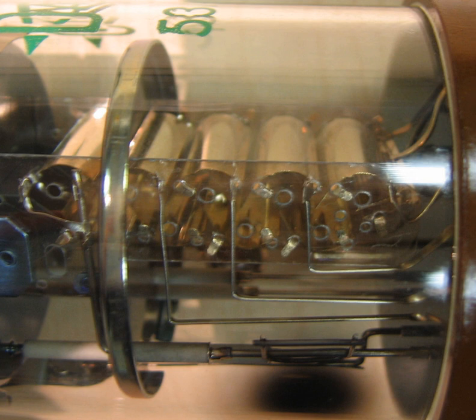The photocathodes can be made of a variety of materials, with different properties. Typically the materials have low work function and are therefore prone to thermionic emission, causing noise and dark current, especially the material sensitive in infrared. Cooling the photocathode lowers this thermal noise. The most common photocathode materials are Ag-O-Cs, also called S1, transmission mode, sensitive from 300 to 1200 nanometers. High dark current, used mainly in near-infrared, with the photocathode cooled.